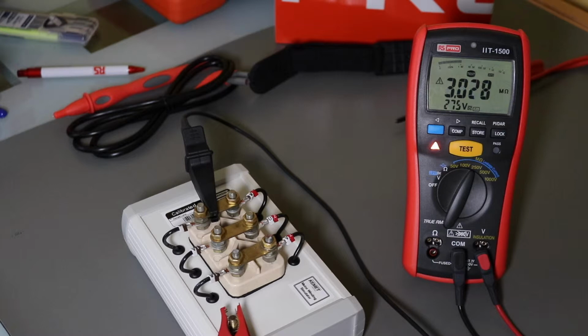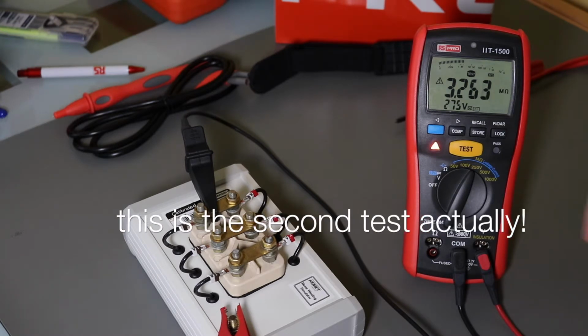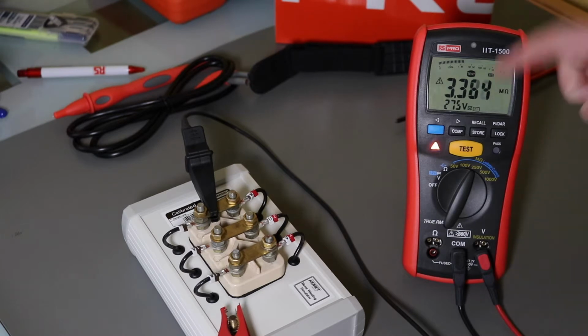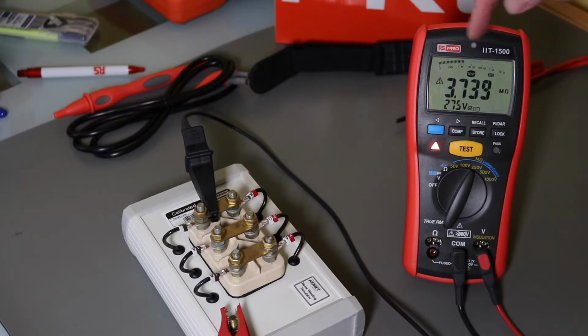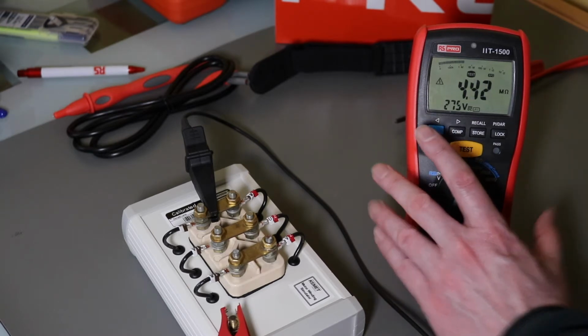Oh boy, this is one of those bad days. Okay, so it kicked off a polarisation index test at 250 volts, although it's showing 275 volts on the display. It's showing it's in test. We've got the hazard warning light to say the voltage is being applied. It's slowly counting up, so we'll leave that for the 10-minute duration to see what results it comes back with.